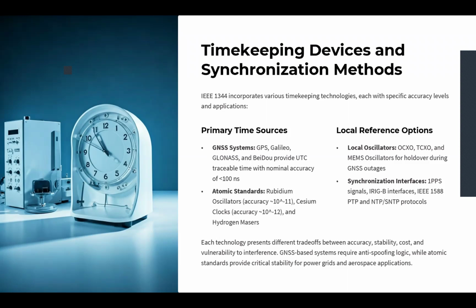When we lose synchronization, so we don't have access to that primary source, the device basically enters holdover mode. We already talked about that. So when we are there, the local references kick in. It could be oven controlled crystal oscillators or temperature compensated crystal oscillators. But what is important is that the maximum allowable holdover drift must be declared based on IEEE 1344. Those devices must log when they enter holdover, so we know when we are disconnected from the primary source of synchronization, and the client must label the timestamps during that degraded mode.